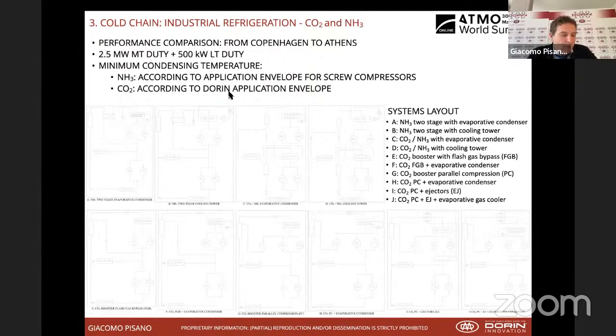And then from an efficiency standpoint, let's try to make a comparison between a large system featuring 2.5 megawatt MT duty, medium temperature, and 500 kilowatt low temperature duty. And let's try to simulate the yearly operation of 10 different systems using ammonia and CO2 in various declinations. So basically we go from a two-stage ammonia system A, then two-stage ammonia with cooling tower, then we go for CO2 cascade systems with ammonia on top with evaporative condenser, then with cooling tower, and then we take into consideration full CO2 systems. From flash gas bypass to parallel compression to ejectors, and then we can also add on top an evaporative gas cooler like adiabatic cooling.